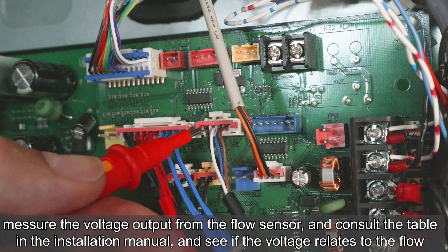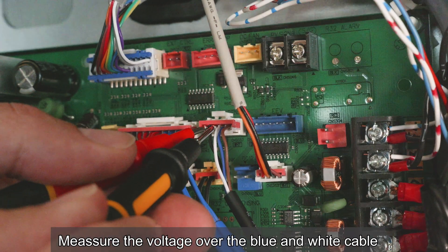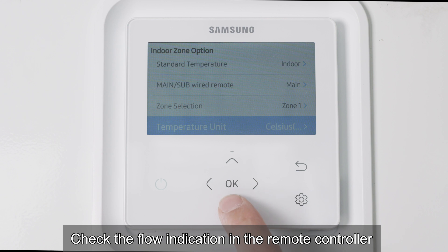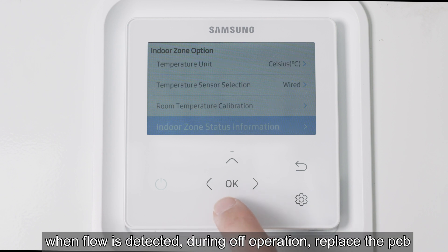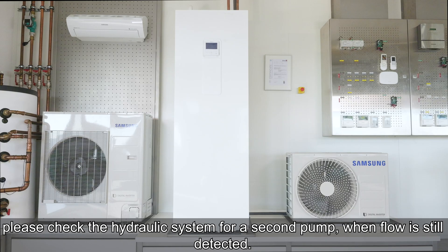Measure the voltage over the white and blue cable. Check the flow indication in the remote controller. When flow is detected during off operation, replace the PCB. Please check the hydraulic system for a second pump.